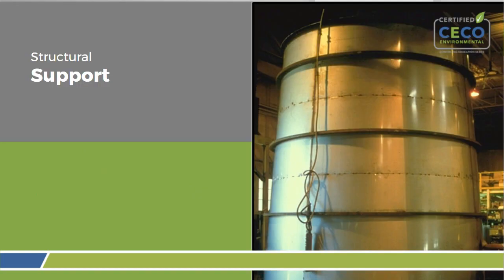This is a 12-foot diameter duct, and since those are 5-foot wide sheets of metal, those stiffeners are on 5-foot centers, and it's important that the duct doesn't collapse, especially if you have a 12-foot diameter duct. You don't want a failure in that duct when it's hanging 20 feet in the air. That could be catastrophic. So flanges can be used as stiffeners.